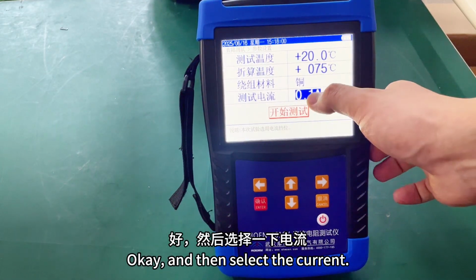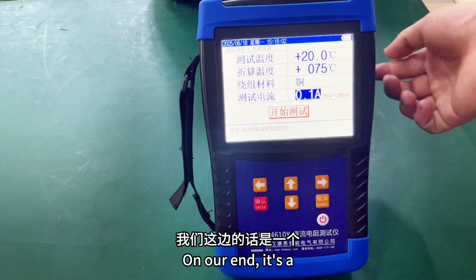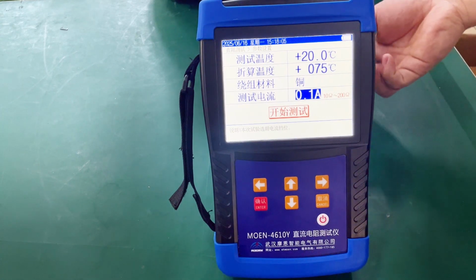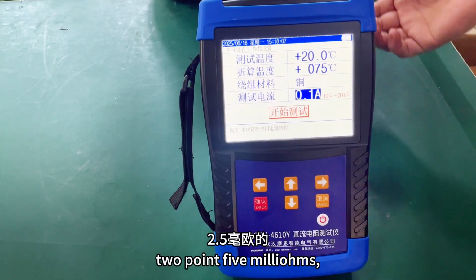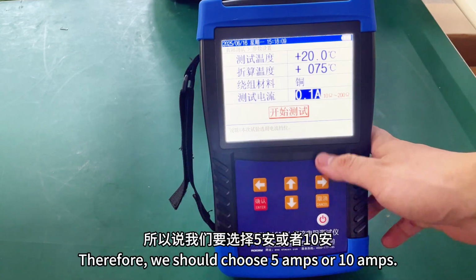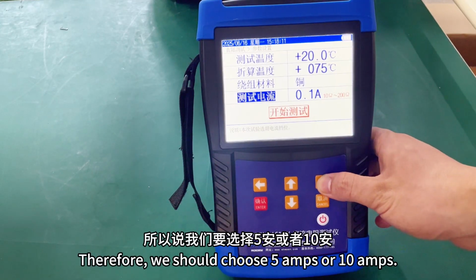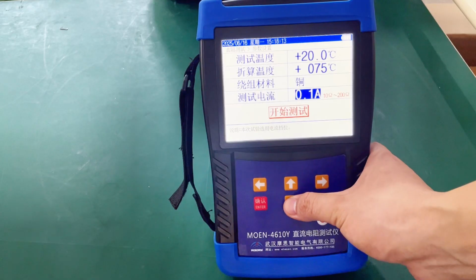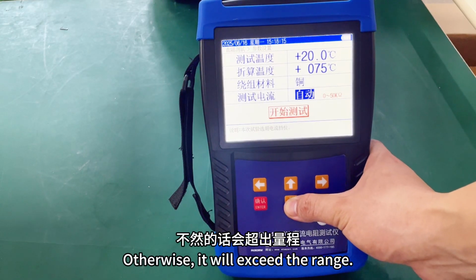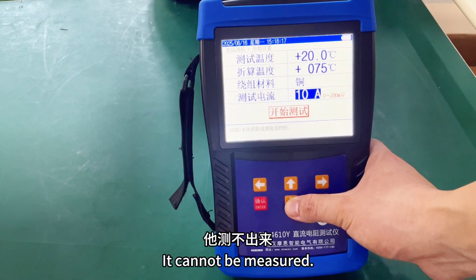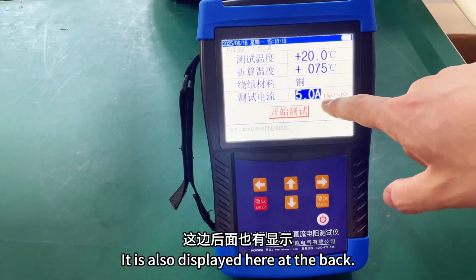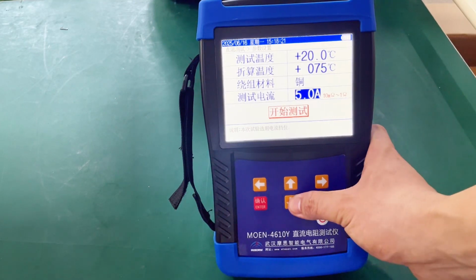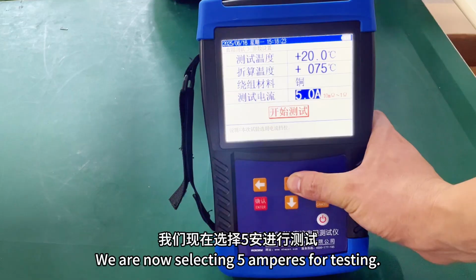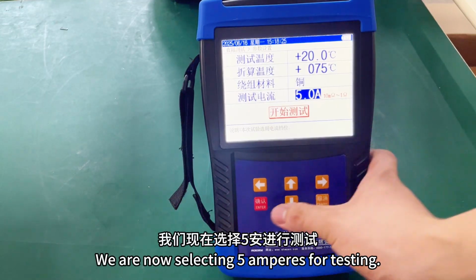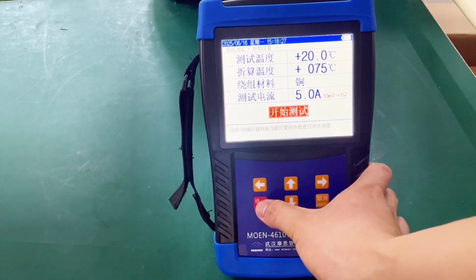OK, and then select the current. On our end, it's 2.5 milliohms. Therefore, we should choose 5 amps or 10 amps. Otherwise, it will exceed the range. It cannot be measured. It is also displayed here at the back. OK, we are now selecting 5 amps for testing. Click OK. Start.